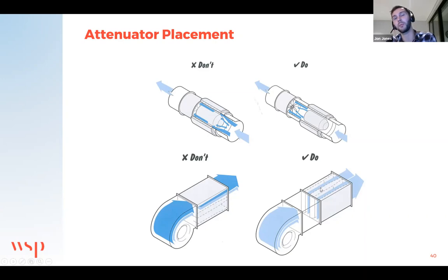But also, on the right, you've got a vertical splitter in the middle here. On the left, these are actually shown horizontally. So again, it helps with the vertical splitters in this sort of arrangement. It helps with the even flow of air across the full face, rather than encouraging all the air through one of the passageways, which is going to give you more regenerated noise and a higher resistance across that.